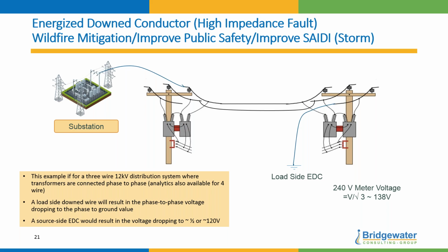Now, we've developed fairly extensive analytics that will determine, with a degree of confidence, whether you have an energized downed conductor. It's been tested on over 500 cases, and we have a pretty good handle on it. On 4-wire, there's a different set of analytics, but it can also be done. One of the applications of this is wildfire. On the West Coast, if a wire goes down in a wildfire area, that is a signal to us to respond. But really the driver in this is public safety. Do you have an energized downed conductor?